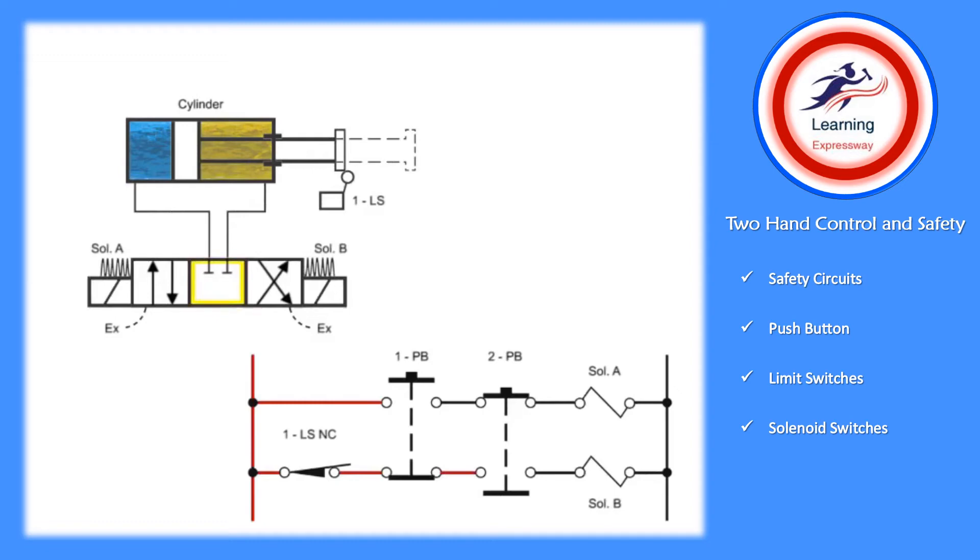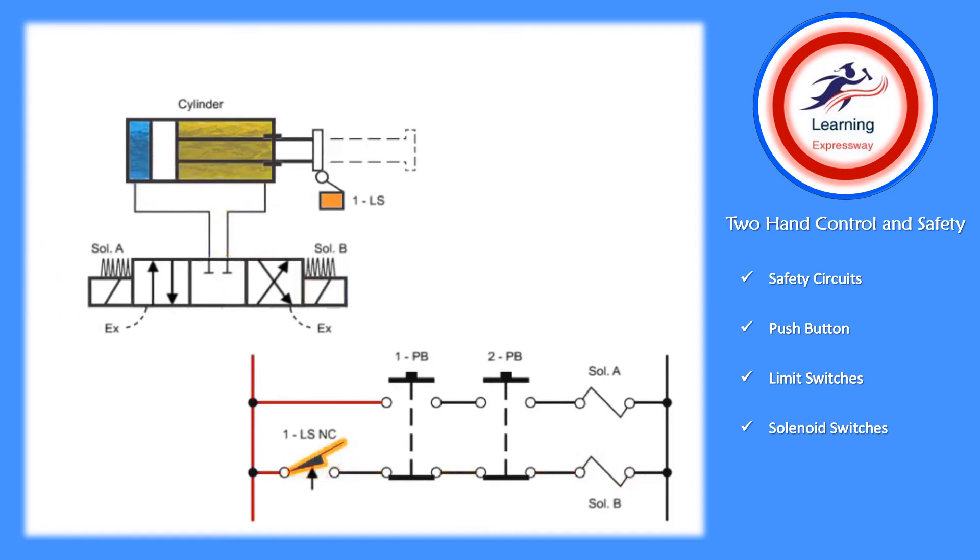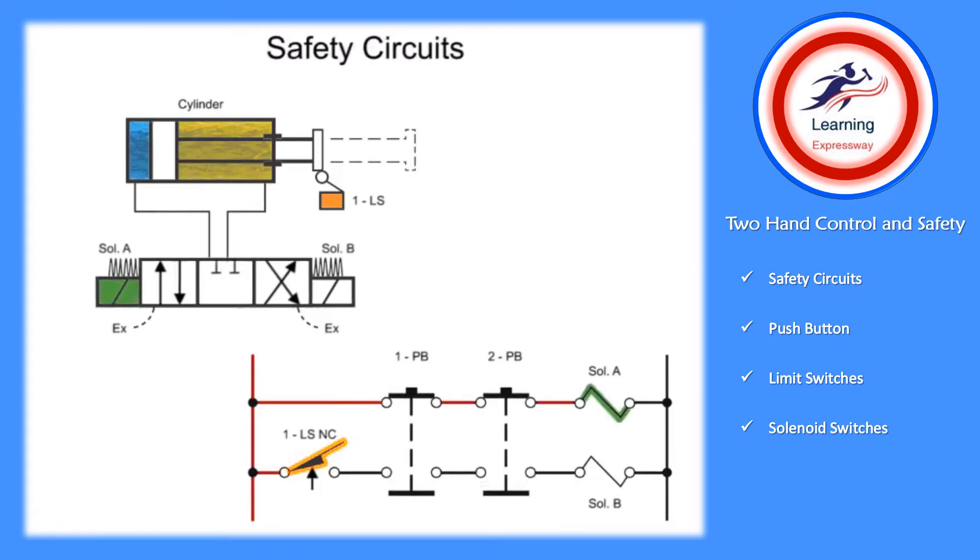If both buttons are released while the cylinder rod is extended, limit switch one allows solenoid B to become energized. The valve will shift to allow fluid into the rod end of the cylinder, causing it to retract. When it reaches the end of its stroke, it engages the limit switch which opens the circuit and prevents electricity from flowing until the two start buttons are engaged once again.